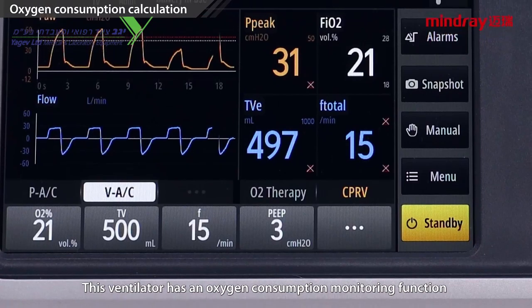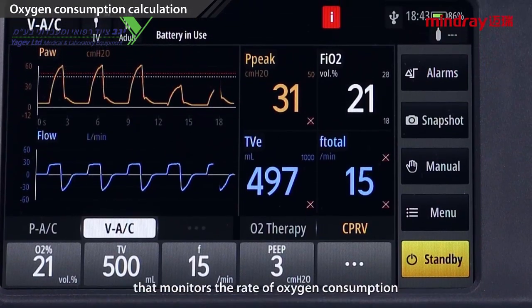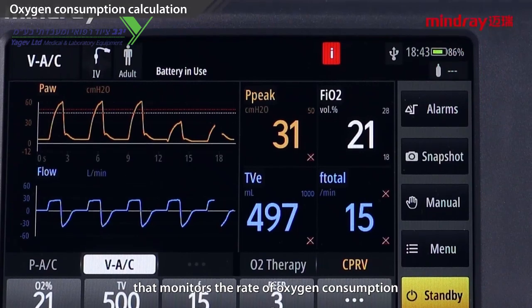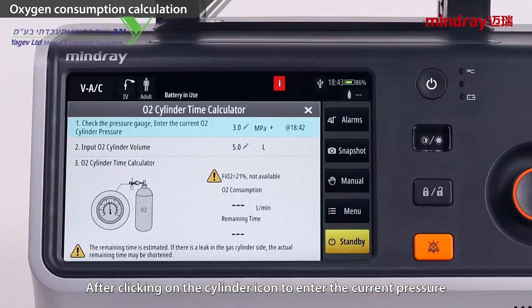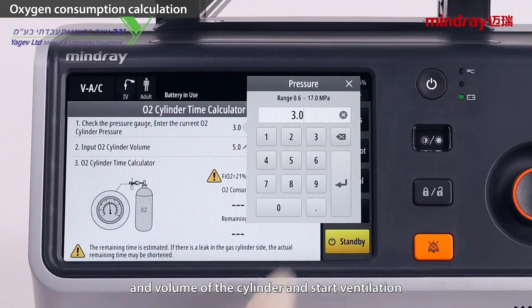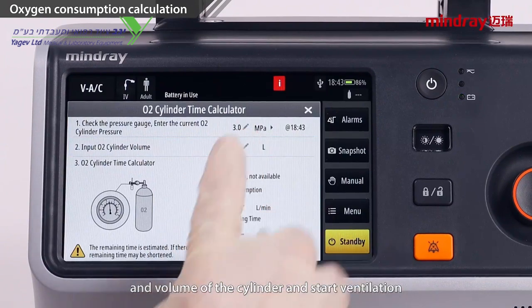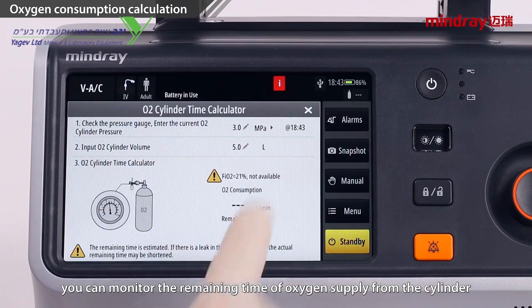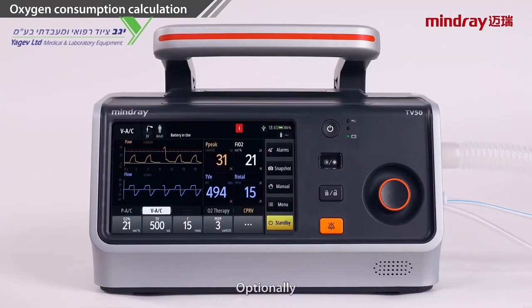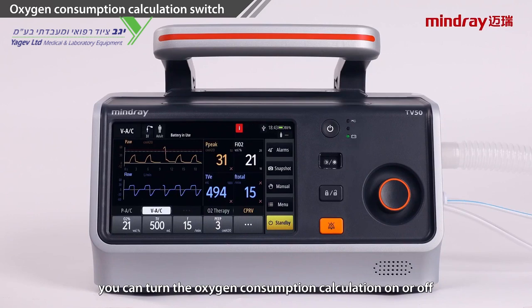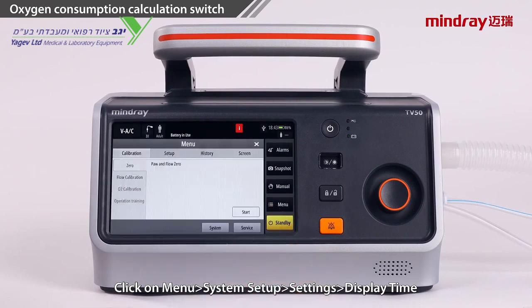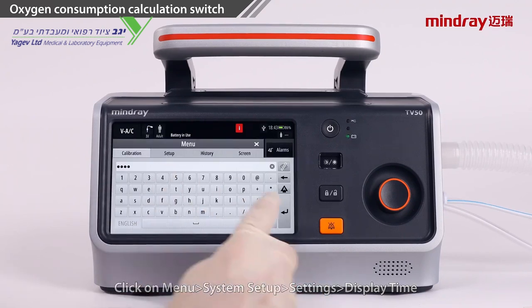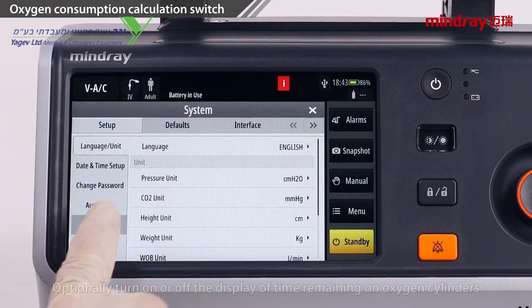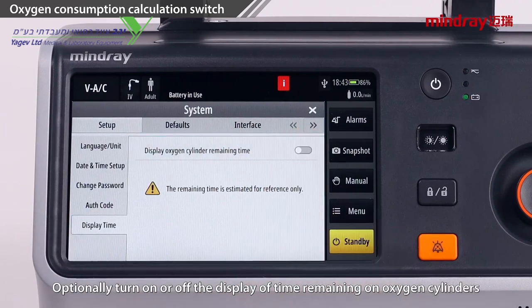This ventilator has an oxygen consumption monitoring function that monitors the rate of oxygen consumption. After clicking on the cylinder icon, enter the current pressure and volume of the cylinder and start ventilation, and you can monitor the remaining time of oxygen supply from the cylinder. Optionally, you can turn the oxygen consumption calculation on or off. Click the menu System Setup, Settings, Display Time. Optionally turn on or off the display of time remaining on oxygen cylinders.